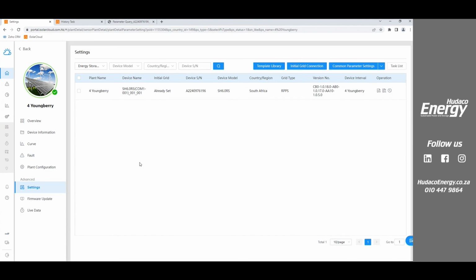The goal for me, though, is we've got to get the wiring right and the settings right. The 6 kilowatt units, they're bulletproof. We've thrown pretty much everything at them. The 10 kilowatt 3-phase units we've had quite a lot of problems with. I think both from an installation perspective and from a settings perspective, where we're right on the limit in a lot of stuff, and we haven't done training like this before. So on the 10 kilowatt stuff, the 3-phase stuff is a lot trickier, and the settings are far more important. I think on the 6 kilowatt stuff, go in, set the settings like you've got them, and the sites are just up and running and working perfectly.